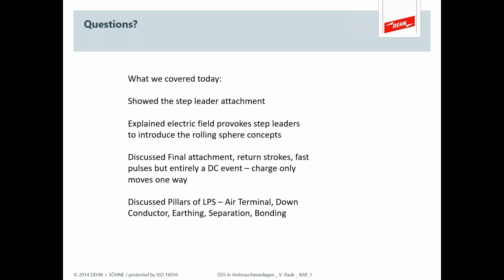Yes. Great question, but the second question we have here is the size of a grounding grid or the size of a grounding rod. Does that depend on the strike energy level, and thus does it also depend on the soil resistivity? That's a great question for our next session, but the answer is yes, it does depend on the strike severity. If you're designing a system to the IEC most rigorous class 1, it will guide you that the depth of that earthing rod needs to be more if you're worried about higher risk levels for the same soil resistivity.